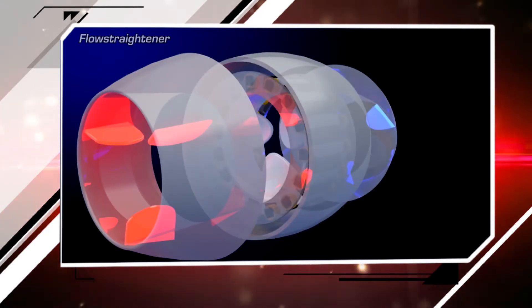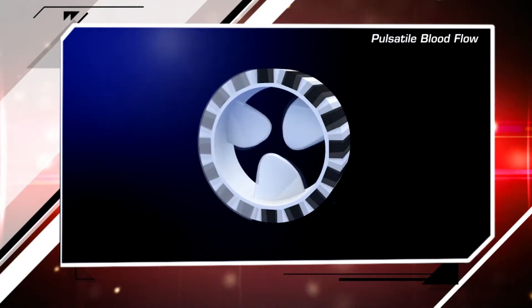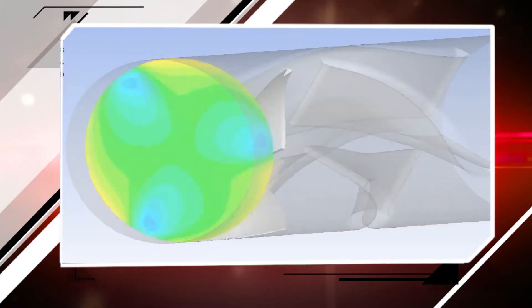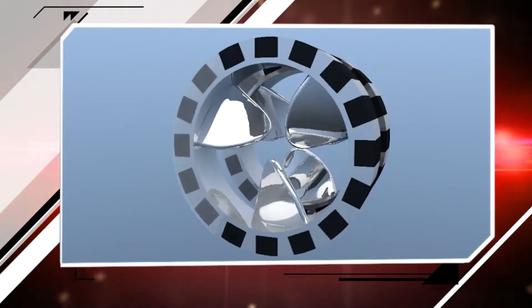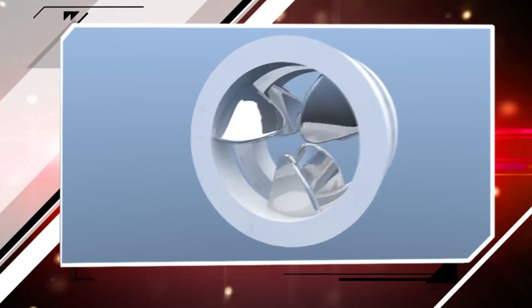This device is the smallest among all other known artificial heart devices. The rotation speed of the rotor is about 3,000 RPM, which is a very critical parameter for not damaging shaped structures of the blood, such as thrombocytes or erythrocytes. The artificial heart is triggered by the detected ECG signal of the patient and provides pulsatile blood flow by start-stop motion.